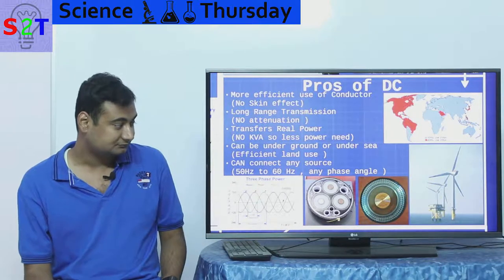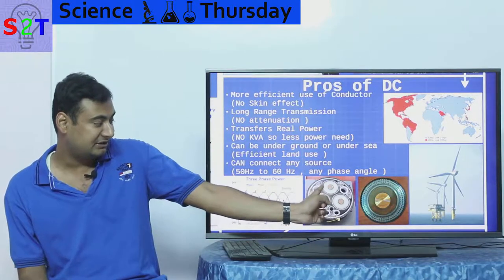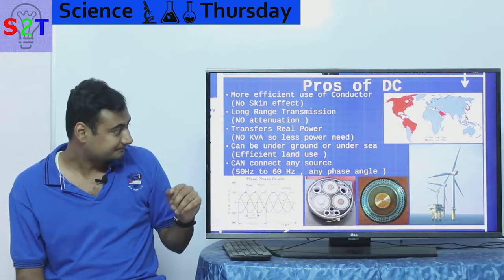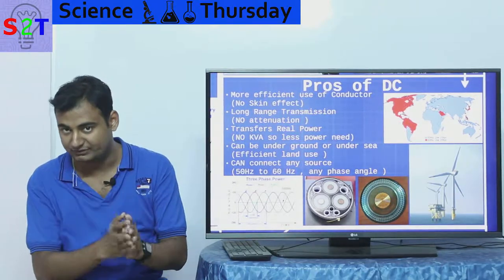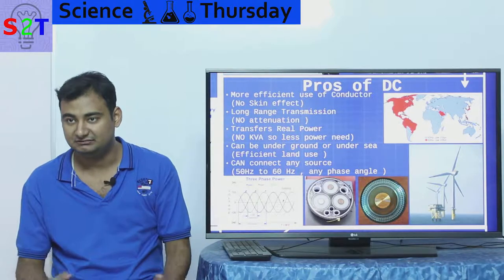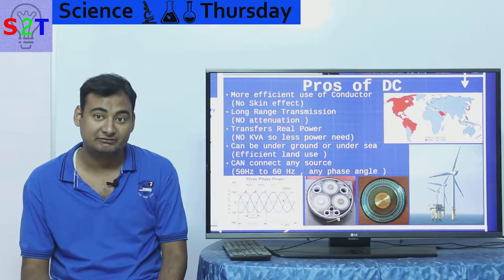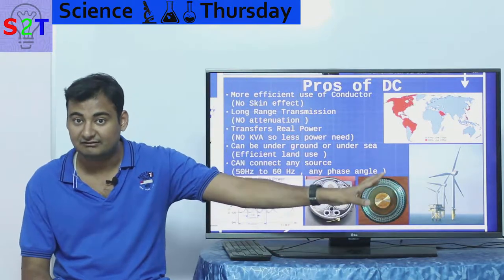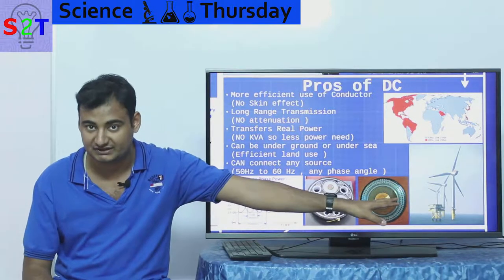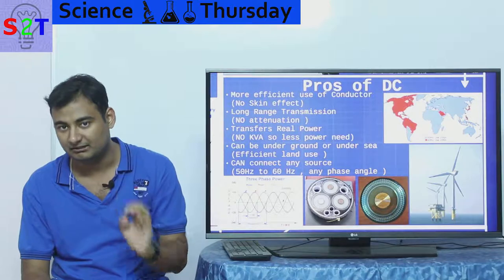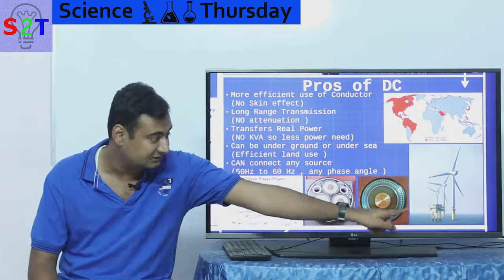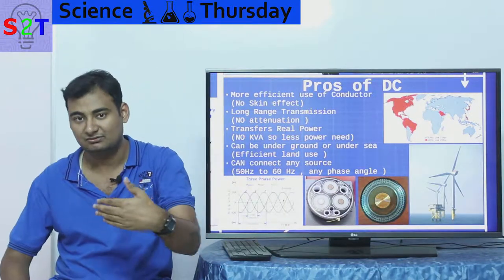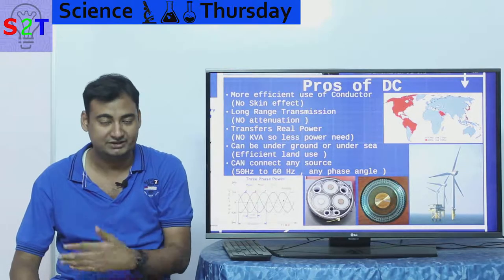DC can also go underground. With AC cable underground you can't make it very thick because of skin effect, but with DC you don't have that problem. It can be easily buried because once it's energized it's not going to bleed energy — it's 30 to 40 percent more efficient per thousand kilometers compared to an AC system. And at sea — such as with offshore wind farms as shown in this picture — they can only send power to shore using a DC system. The turbines make AC which travels a very short distance to a switching station, then it's converted and sent as DC, which could be as long as 600 kilometers to shore. That cannot be done on AC.